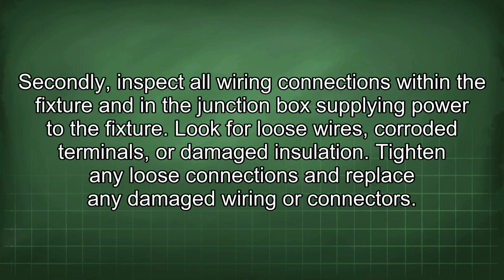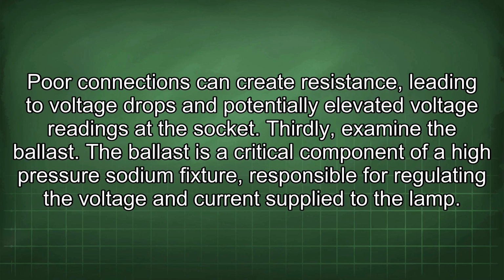Secondly, inspect all wiring connections within the fixture and in the junction box supplying power to the fixture. Look for loose wires, corroded terminals, or damaged insulation. Tighten any loose connections and replace any damaged wiring or connectors. Poor connections can create resistance, leading to voltage drops and potentially elevated voltage readings at the socket.